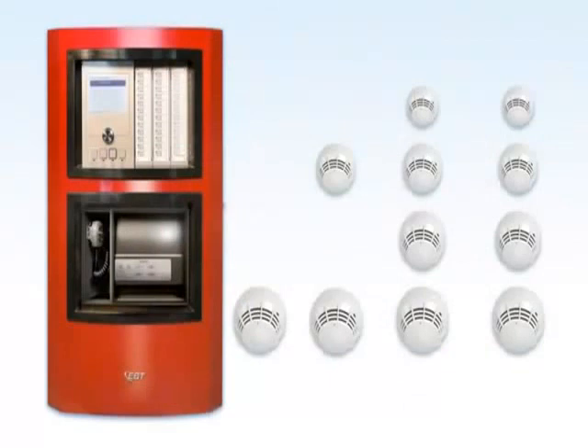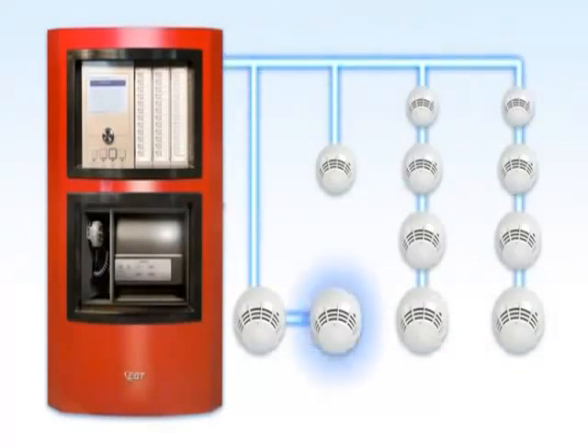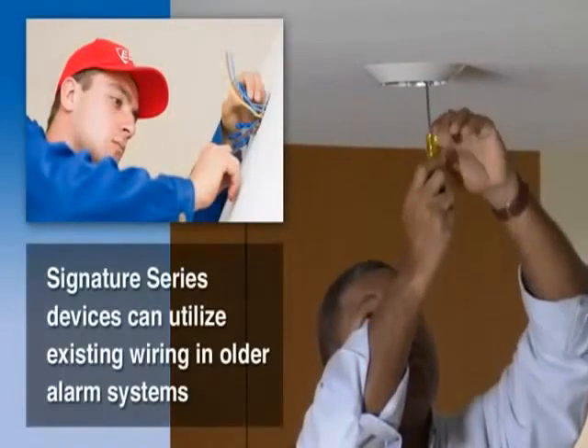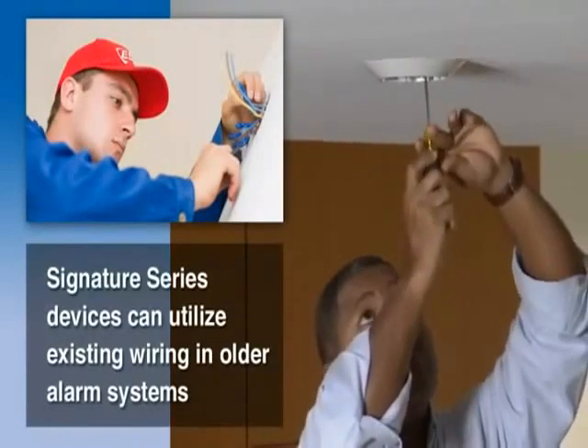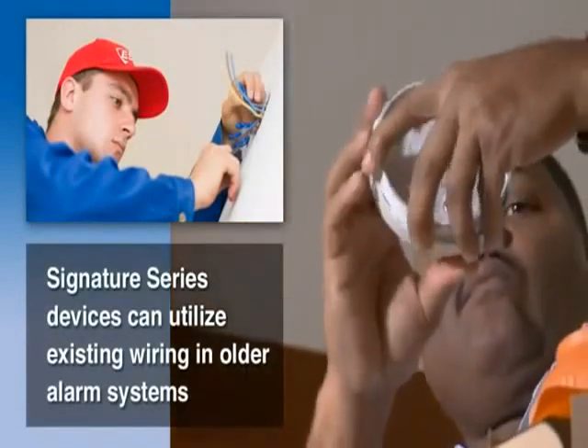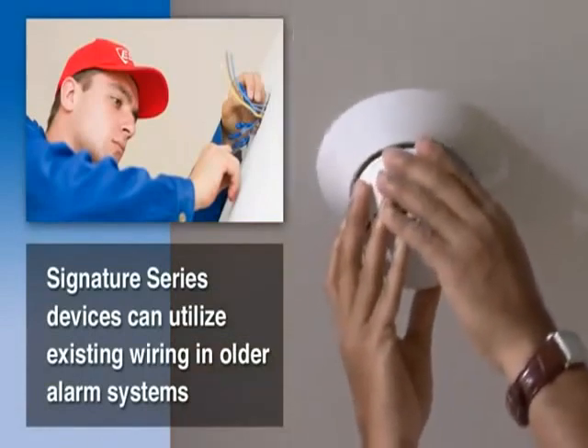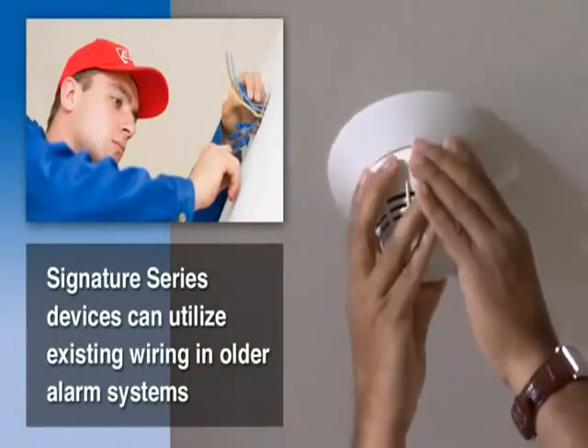With our Signature Series having the ability to have distributed intelligence, the one thing we do that's very unique in our industry is we provide what's called polling by exception. And what polling by exception means is since the detector is making its own decisions, the panel is not overburdened with a bunch of information passing back and forth. In most cases, the new Signature Series devices can also utilize the existing wiring found in old alarm systems, saving significant time and costs during a retrofit upgrade.